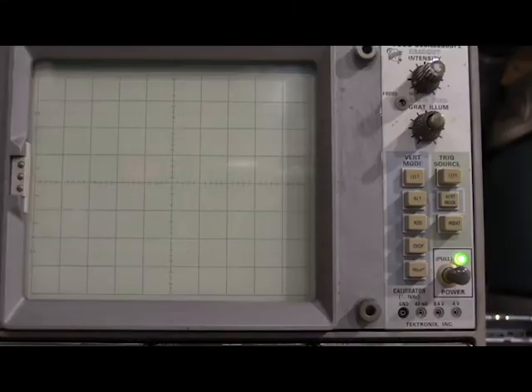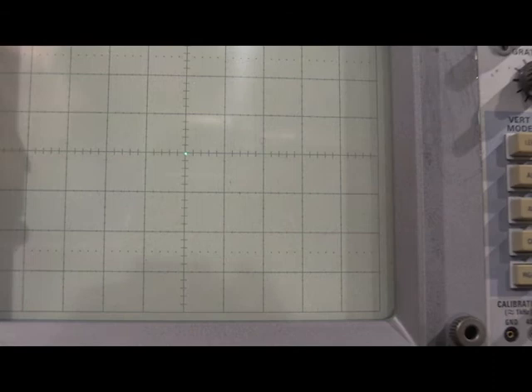I'll get set up for the horizontal amplifier setting. Okay, I'm going to adjust the horizontal centering control. This particular one needs the calibration fixture in the horizontal compartment, and I am looking for the dot. The dot needs to line up with the center line, right about there. That looks good.